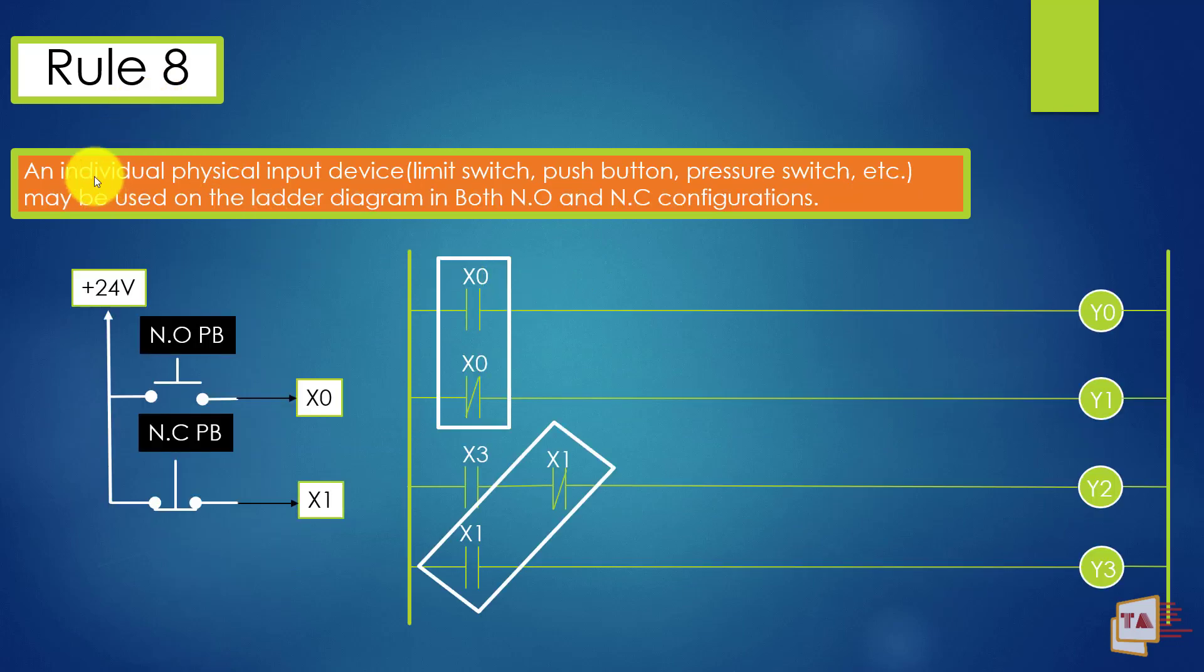See here next rule: an individual physical input device, limit switch, push button, pressure switch, etc., maybe used on the ladder diagram in both NO and NC configurations. This is a very important rule. This is a field wiring. We have normally open push button connection on X0. This is the normally open. Normally open means when you press the push button, then supply will come from the point. So X0 will get turned on. See, X0 is normally open in field, but in ladder diagram, you can use it in NO or NC. Both ways you can use, in both configuration, you can use the X0.